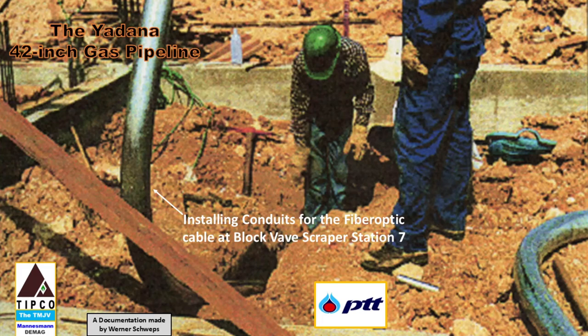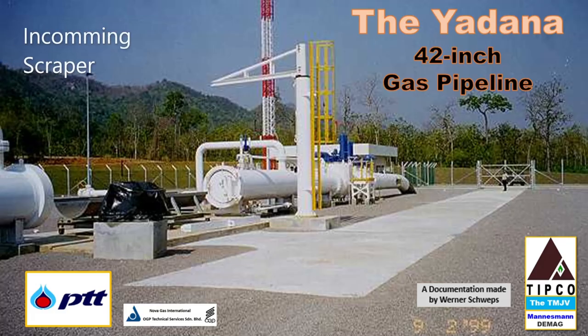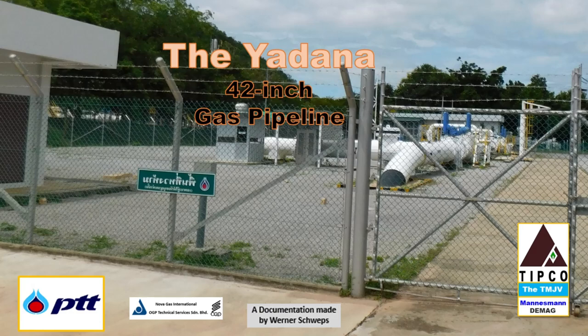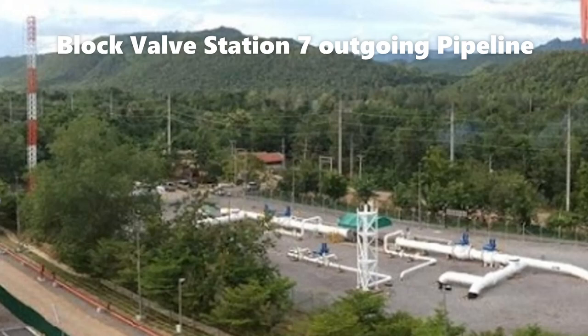These RTUs also facilitate the remote operation of all the valves in the scraper piping system by allowing remote control commands to open and close the valves, as well as to indicate their current positions within the piping system for the scrapers and the station bypass. Additionally, the SCADA system includes a feature for the remote operation of an emergency pipeline shut down by closing the 42-inch buried mainline block valve installed in the station bypass.